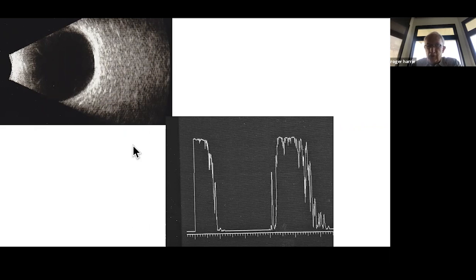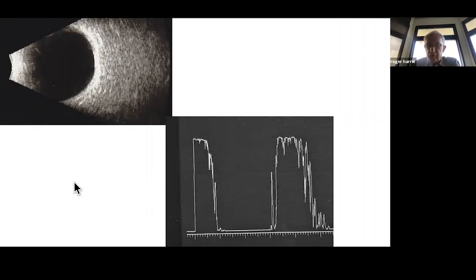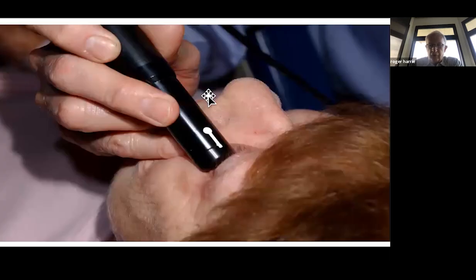The speaker trained with Dr. Carlos Ossoinig, who developed the A-scan in Austria before coming to Iowa. The diagnostic A-scan he developed is a freestanding unit with an S-shaped amplification curve — not logarithmic — that optimizes signal capture in the middle of the curve. This freestanding A-scan is fundamentally different from the vector A-scan derived from B-scan data.